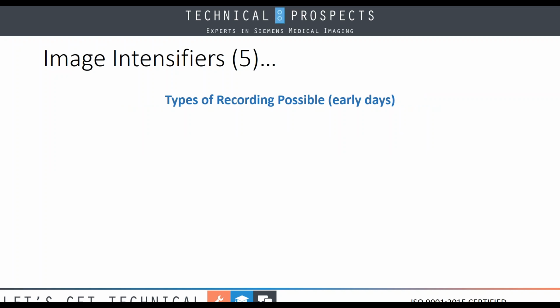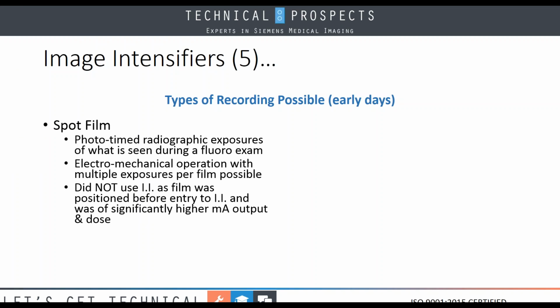Now, with these outputs, we did all sorts of different recordings and stuff. The biggest one that was possible, we can thank our lawyers for, and that was something called spot film. What was going on, if you think about the overall operation of a fluoro exam, these were performed by the radiologist by themselves in the room, and they're seeing what's going on in the patient. Well, like anything else, how do I know what you saw, doc? Where's your proof? So what the industry did is they came up with a device called the spot film device. And back in the day, this was an absolute electromechanical nightmare.